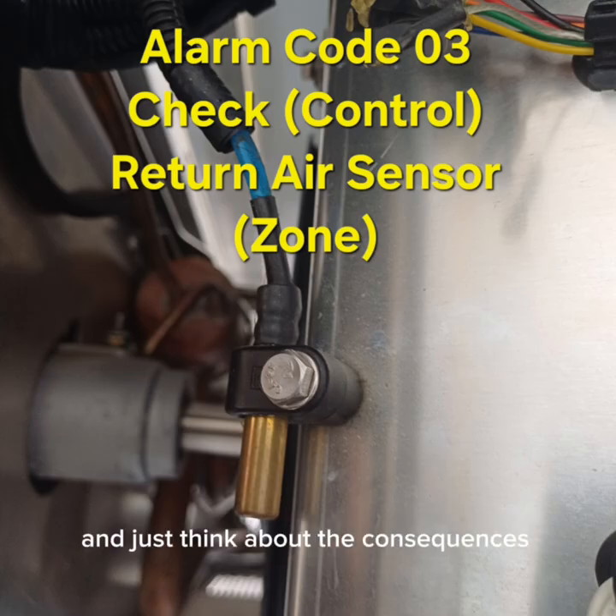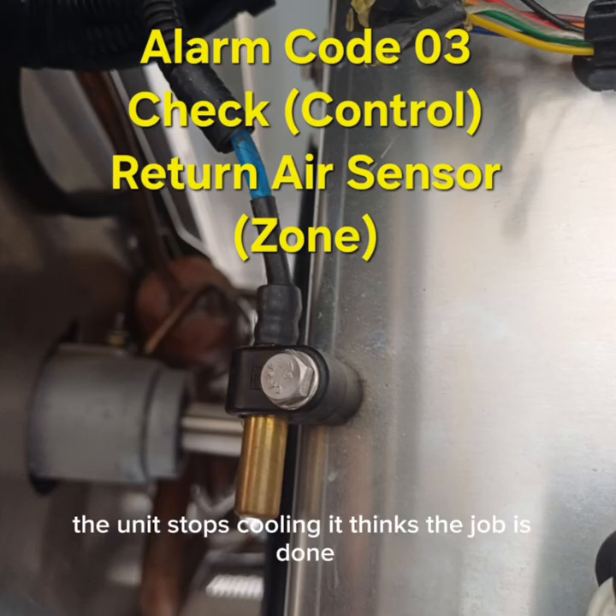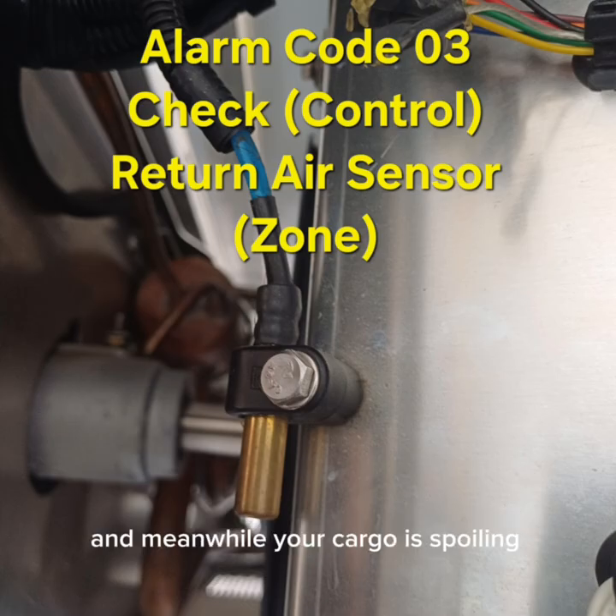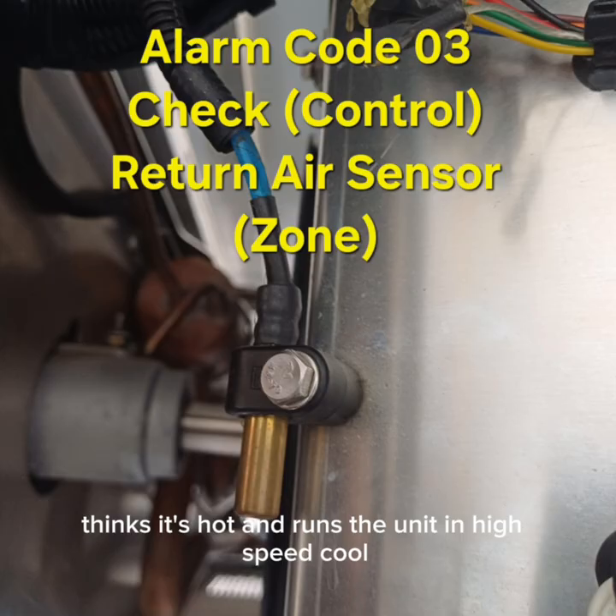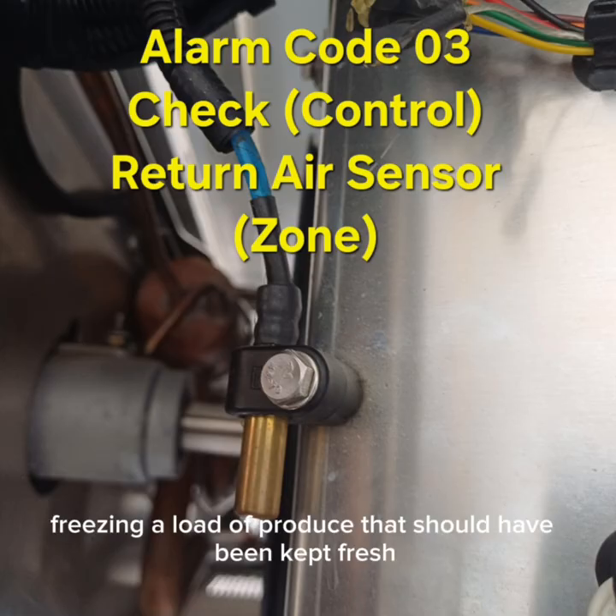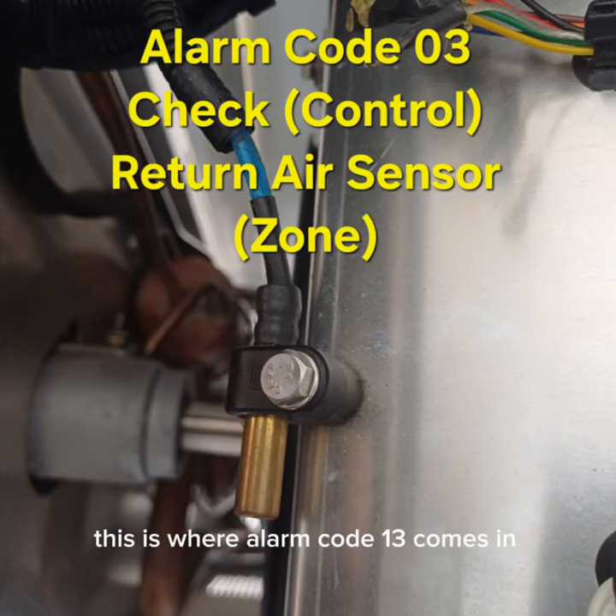Right. And just think about the consequences. If the sensor reads low, it tells the unit, hey, it's 30 degrees in here, but it's actually 45 degrees. The unit stops cooling. It thinks the job is done. And meanwhile, your cargo is spoiling. Or the reverse, it reads high, thinks it's hot, and runs the unit in high-speed cool, freezing a load of produce that should have been kept fresh. This is where alarm code 13 comes in, isn't it? Exactly.